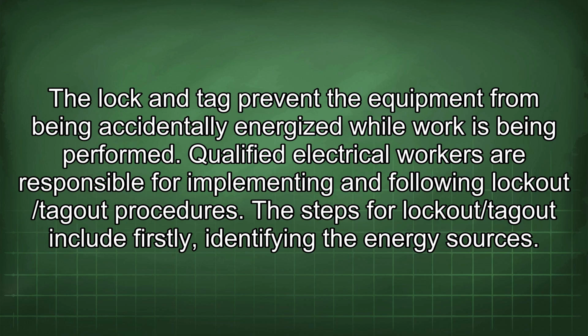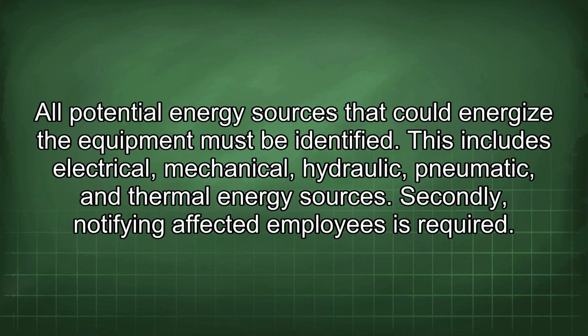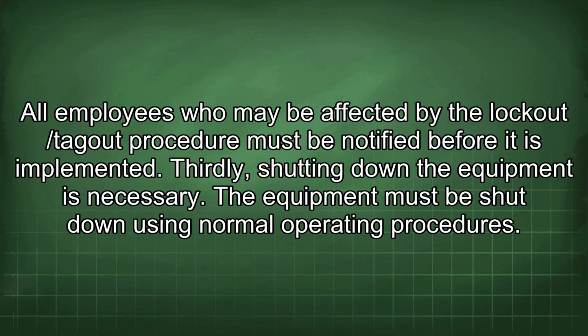The steps for lockout/tagout include, firstly, identifying the energy sources. All potential energy sources that could energize the equipment must be identified. This includes electrical, mechanical, hydraulic, pneumatic, and thermal energy sources. Secondly, notifying affected employees is required. All employees who may be affected by the lockout/tagout procedure must be notified before it is implemented. Thirdly, shutting down the equipment is necessary. The equipment must be shut down using normal operating procedures.